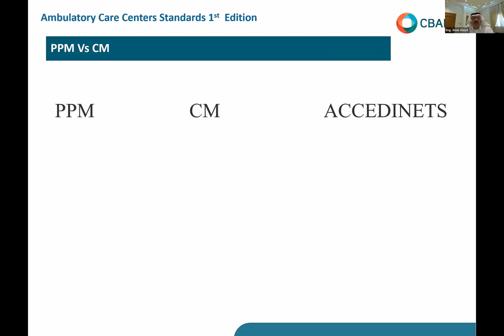Now, the standard talks about PPM versus CM. Why standards? Why do we need PPM in the center? Why do we need preventive maintenance? Why don't we just do corrective maintenance? Why is the standard concerned about PPM and corrective maintenance? Now, this is a requirement in this standard.